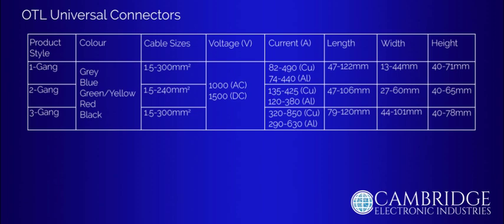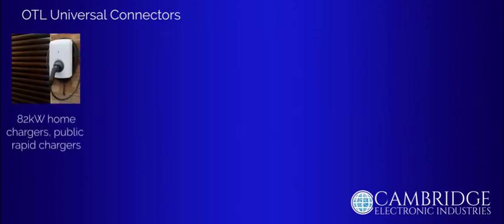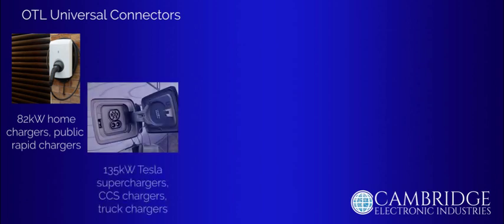The connectors offer a high voltage and high current range, making them ideal for high power applications. At the lower end of the scale, the 82 kilowatt connector would be used for most vehicle charging applications, including DC fast charging, known as public rapid chargers, and the combined charging system, which uses both AC and DC power. This power level is predominantly used in EV chargers to the home. The larger 135 kilowatt scale offers connectivity to the high power requirements of rapid chargers and the Tesla superchargers. In Europe, the main rapid charging system is delivered by the combined charging system using the DC power range.